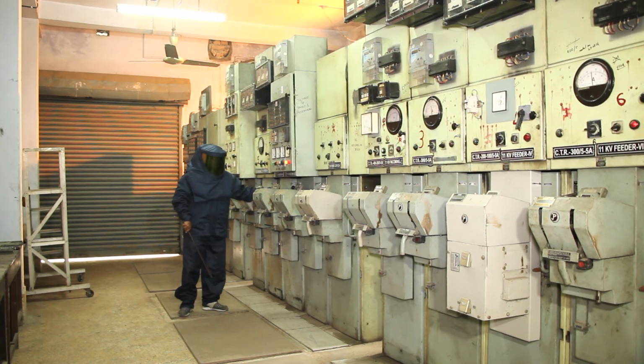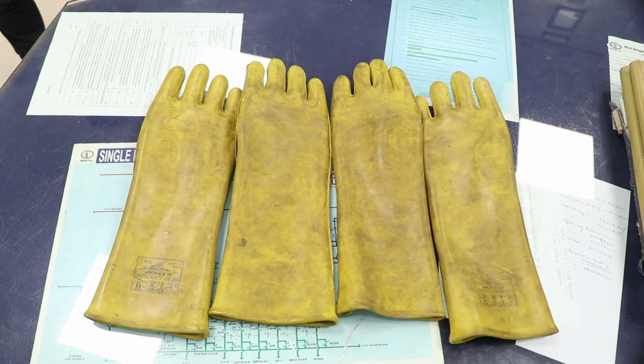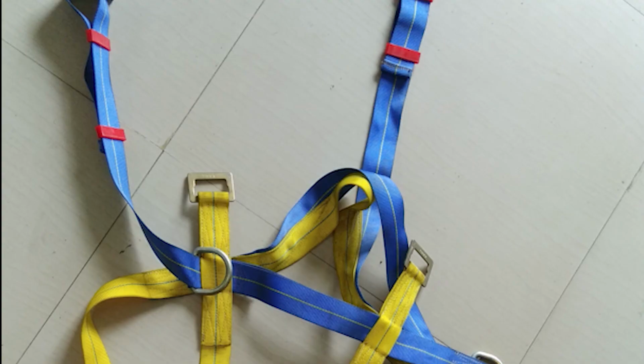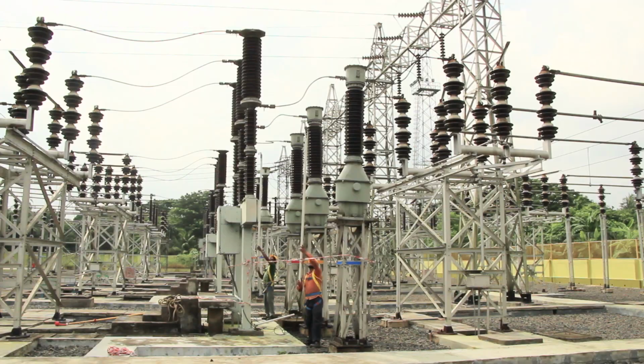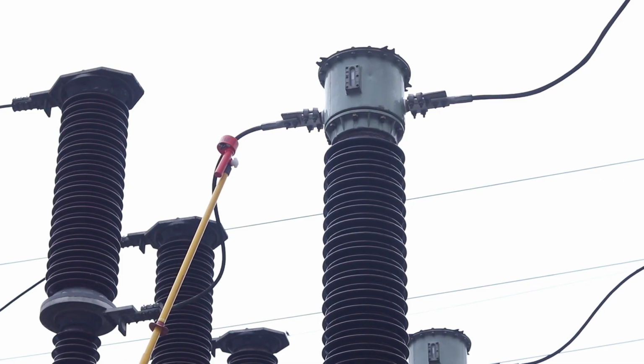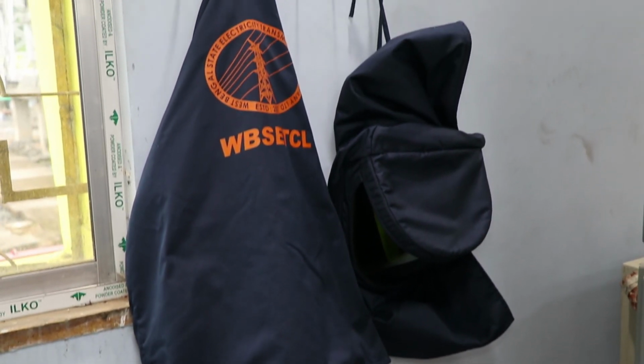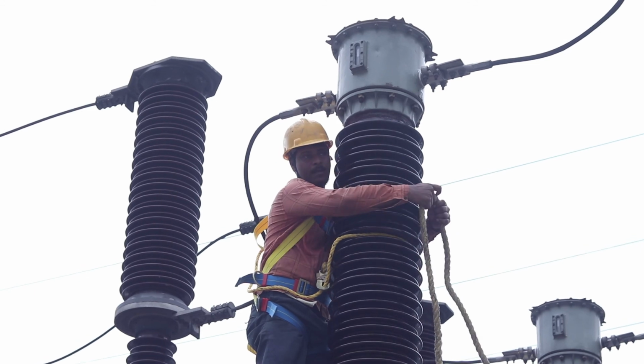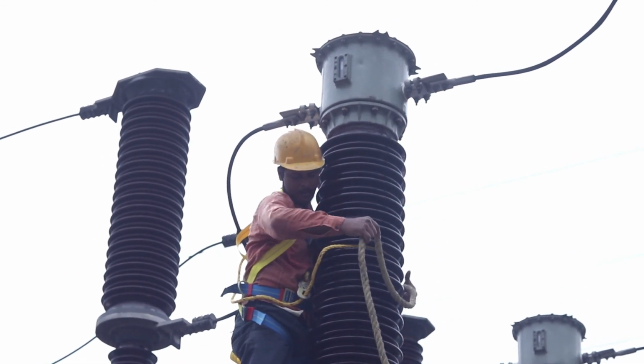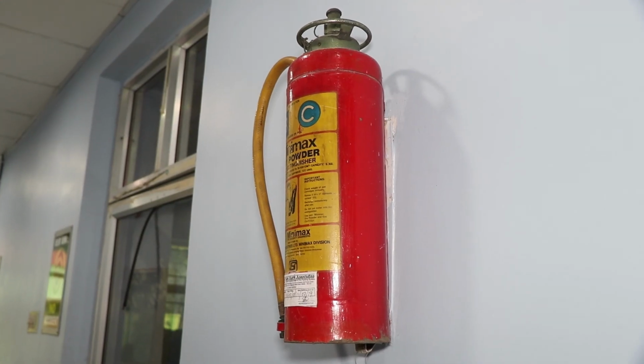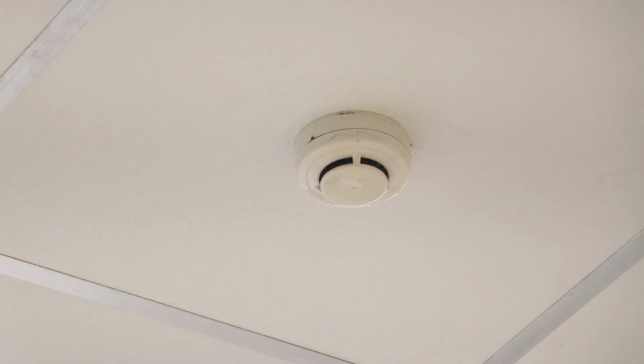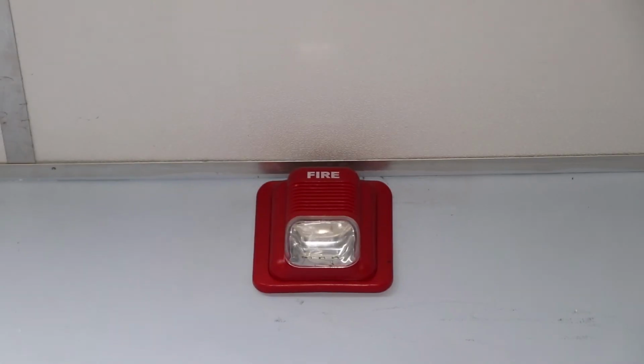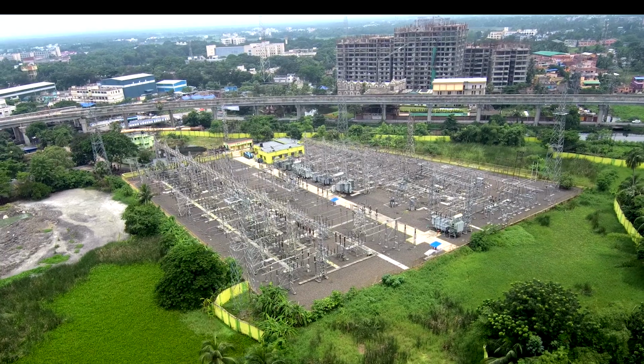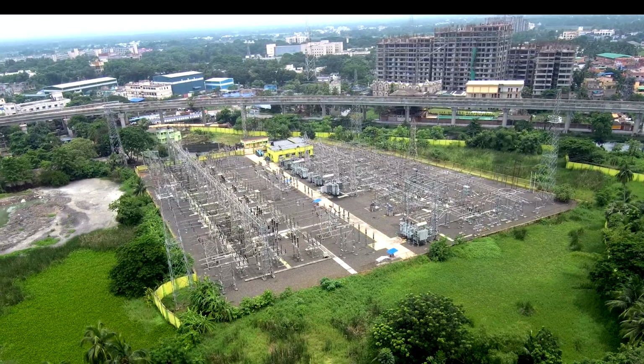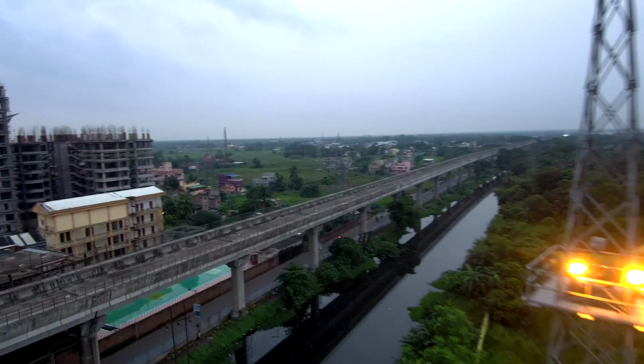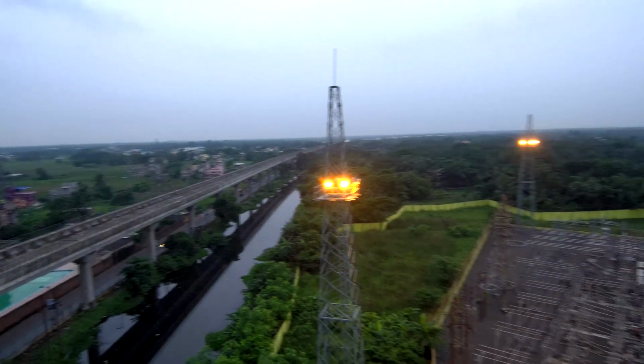Proper safety equipment such as safety helmet, safety gloves, gumboot, safety belt and harness, earth rod, HV detector, arc flash suit are used to minimize hazards. Safe operating procedure is maintained here before any operation. Fire extinguisher and smoke alarm system is installed at working zone to ensure fire safety. Four numbers of mast towers are constructed within the switchyard premises for protection from lightning. Sufficient sodium vapor lamps are used for lighting purpose during night hours.